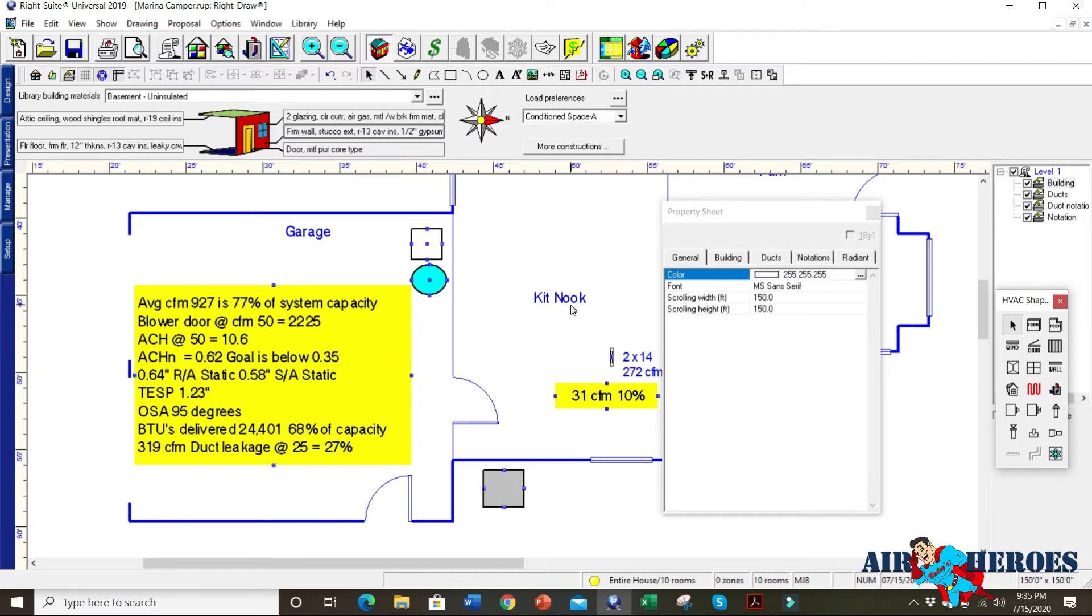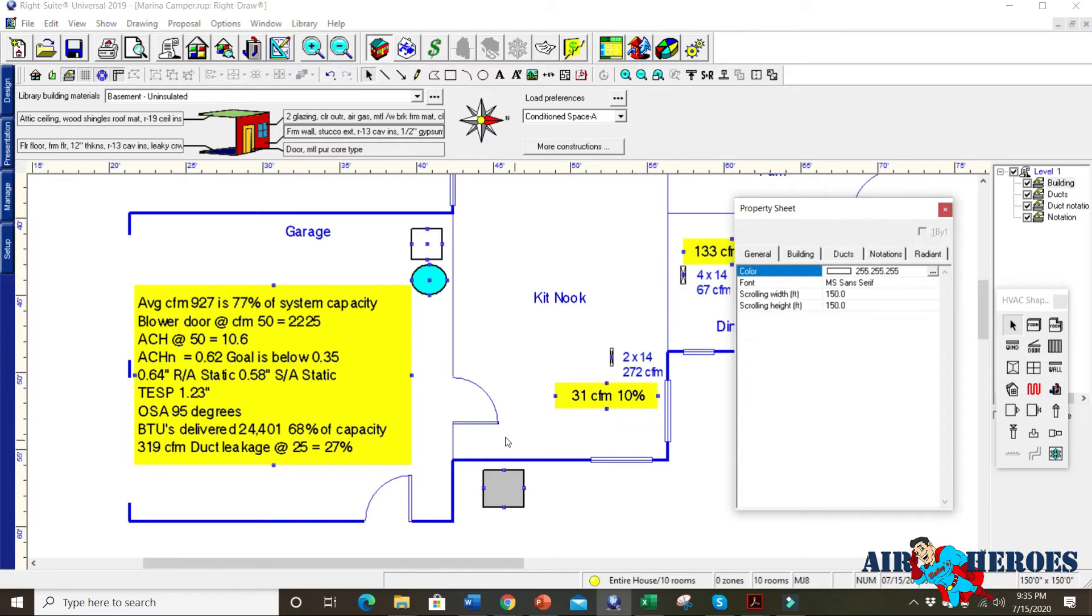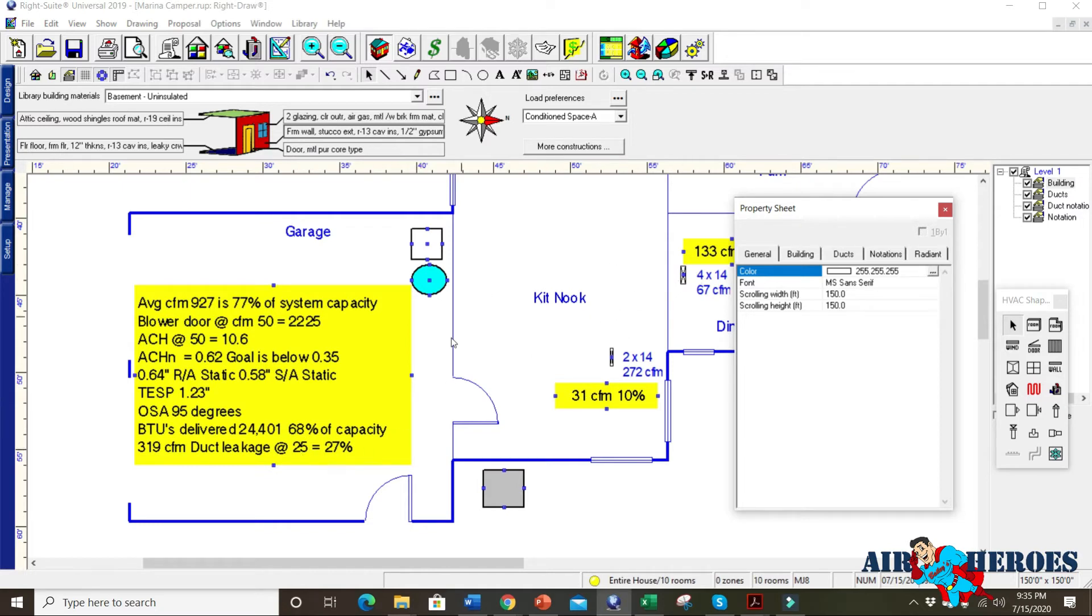They also have R19 insulation for the attic. We take and change the insulation, fix the can lights so they're not leaking and fix the duct leakage and the air delivery to get that dialed in. They don't need a new system. They just need all this stuff fixed.